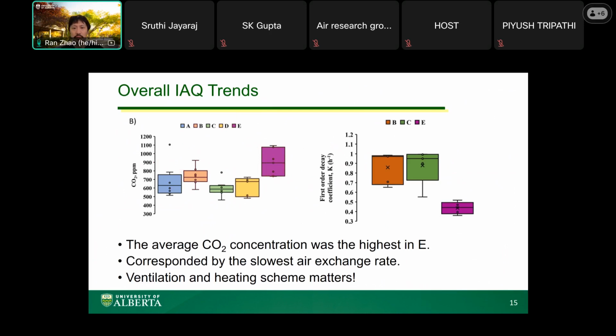We used the data to derive the air exchange rate. Every time there's an event going on indoors, there's a spike in CO2 or particulate concentration, followed by a first order decay, and that decay rate corresponds to the air exchange rate. From the data, we calculated that first order air exchange rate in units of per hour. The diagram on the right shows this first order air exchange rate in buildings B and C versus E.